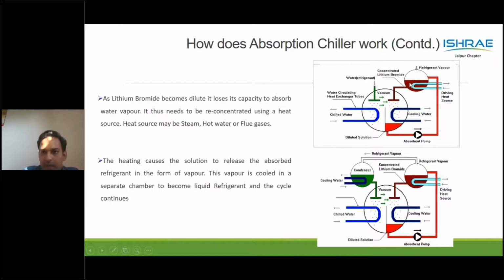This solution is heated. Now lithium bromide has a boiling or vaporizing point of over 1000 degrees Celsius, so it does not evaporate. All the water vapors in the lean solution get evaporated and separate out, leaving the concentrated lithium bromide behind, which goes back to my absorber.